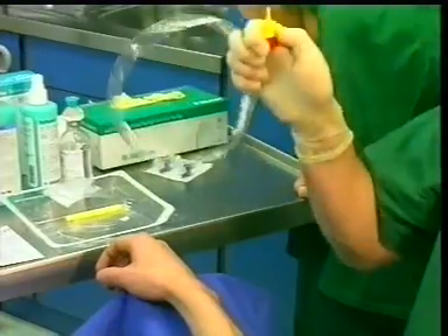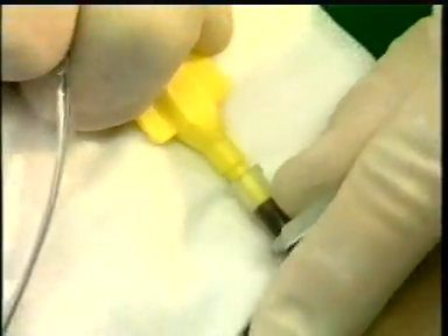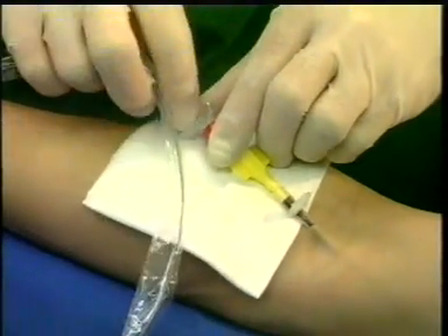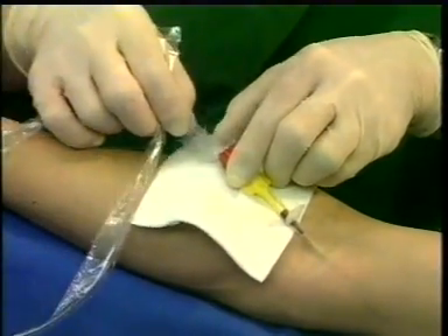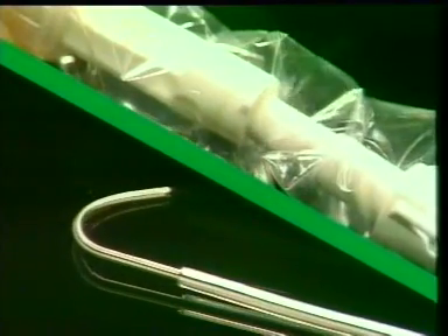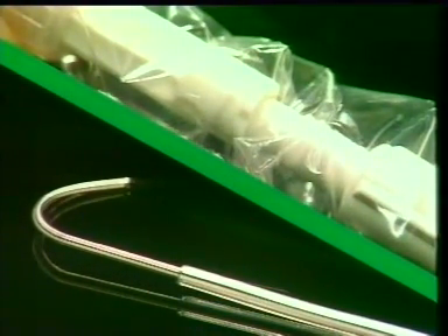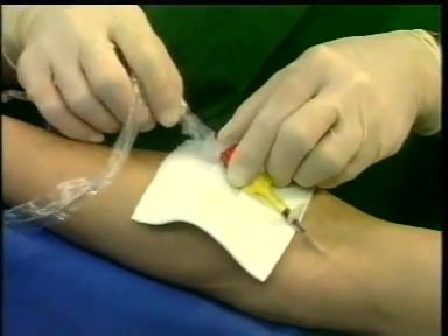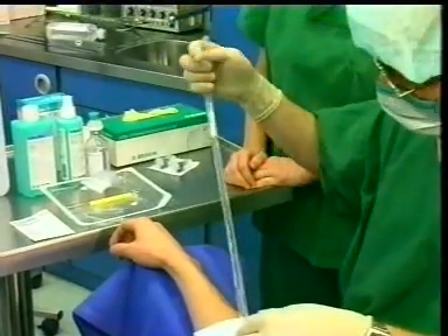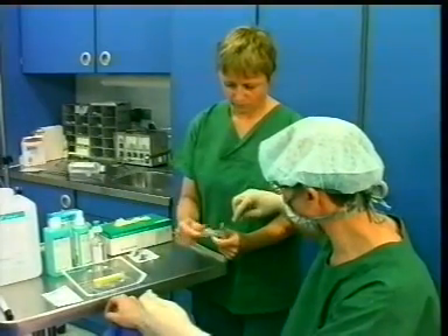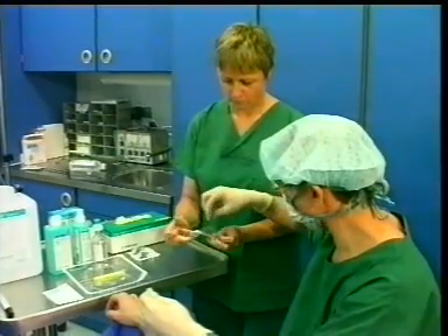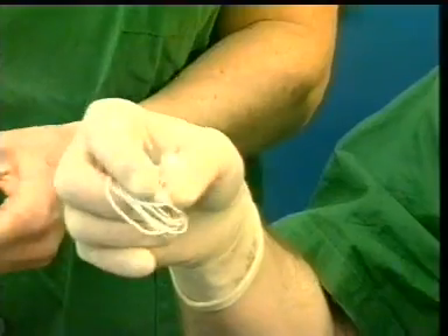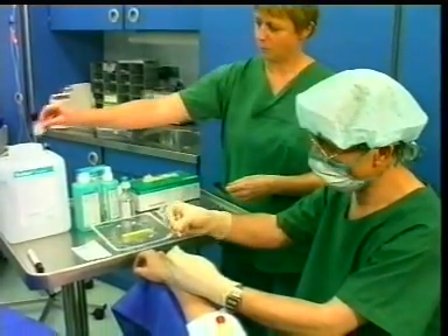After taking off the protective cap, the catheter connector is attached to the plastic cannula. The catheter is held lying flat and advanced from within its protective sheath. After that, the guide wire is connected to the catheter hub so that the J-tip of the guide wire extends beyond the tip of the catheter. This improves the passage of the catheter through the venous valves, avoids venous lesions, and optimizes the subsequent transmission of the ECG signal. In the protective sheath, the catheter can be advanced or retracted without endangering sterility. The end of the sheath is pulled tight over the ECG socket to ensure good contact with the connection cable. The connection cable is attached to the guide wire of the catheter.